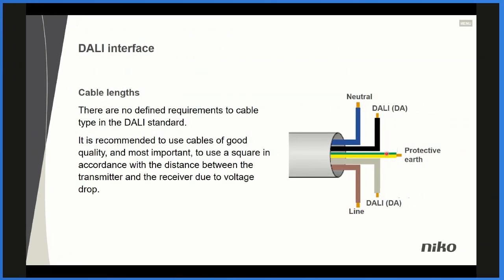About the cable, use a standard 5-wire cable, and make sure that you have the line with the brown and then the neutral, which is the light blue here, and then the protective earth, which is the green-yellow color, and then you have the 2 DALI bus lines. It could be the black and the gray one. As you can see here, there's no plus or minus because it's polarity free. So it's up to you. But choose a cable of good standard, because due to the voltage drop, a maximum of 2 volts drop is allowed on the DALI bus.